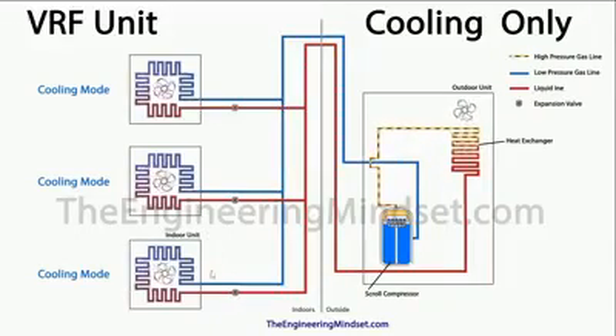Now on each indoor unit, and as I said, these are the cassette versions, so each one employs an electronic expansion valve. This is currently the most advanced version of a thermal expansion valve, and this is what meters the amount of refrigerant flowing into the indoor unit, into the heat exchangers. So the electronic expansion valve is constantly taking readings for this heat exchanger to limit how much refrigerant flows into there to match the exact cooling requirements. On the indoor unit, we've also got a fan inside these, and that pulls air from within the room and pulls it across and blows that across in all directions across this heat exchanger, which contains the refrigerant. The refrigerant is always held within it, it never leaves the system.